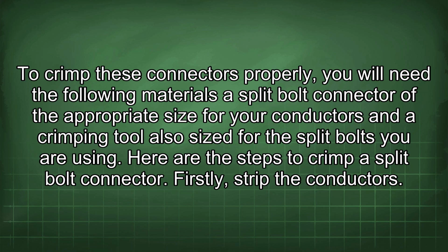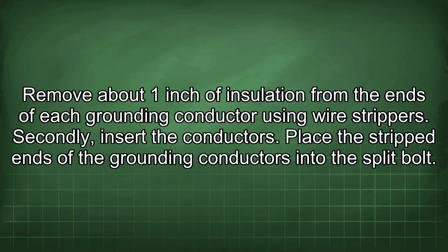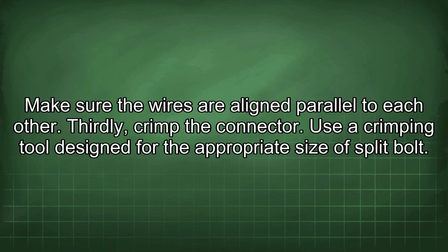Firstly, strip the conductors. Remove about 1 inch of insulation from the ends of each grounding conductor using wire strippers. Secondly, insert the conductors. Place the stripped ends of the grounding conductors into the split bolt. Make sure the wires are aligned parallel to each other.